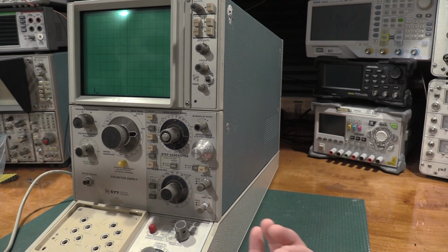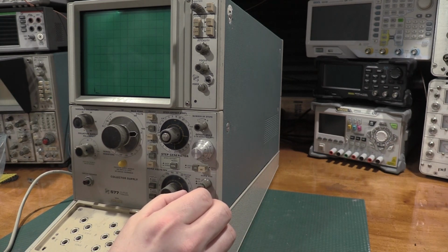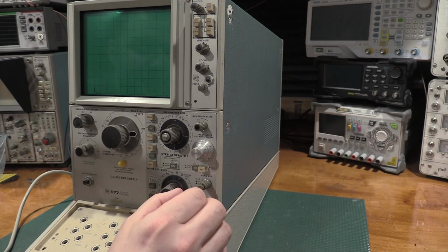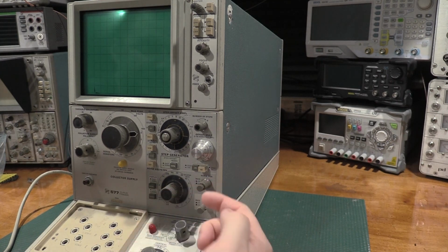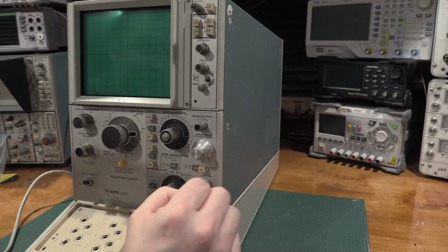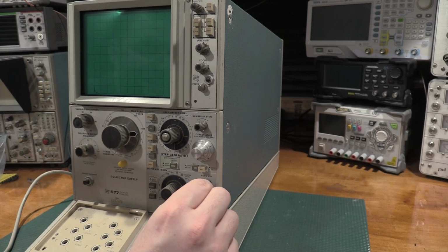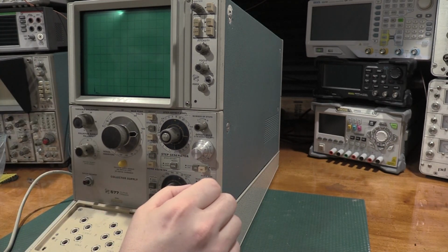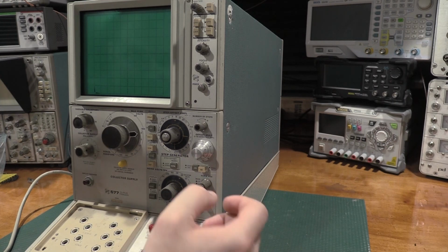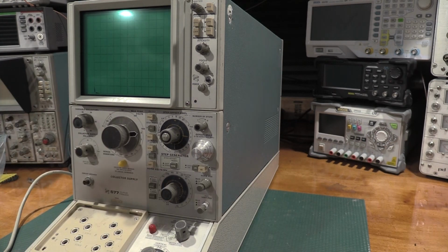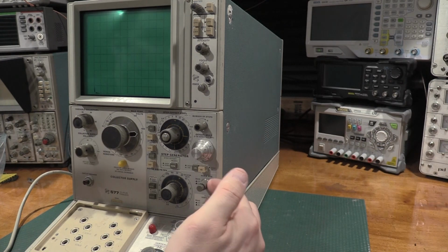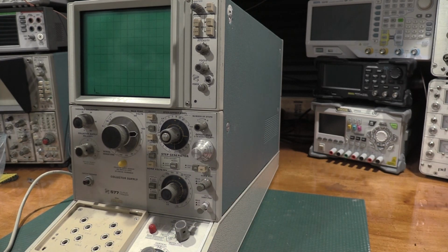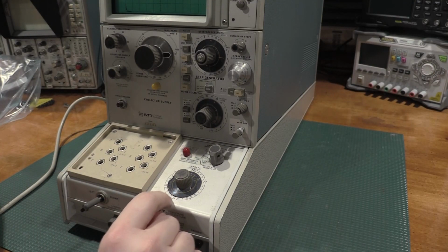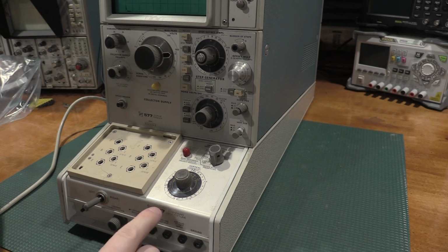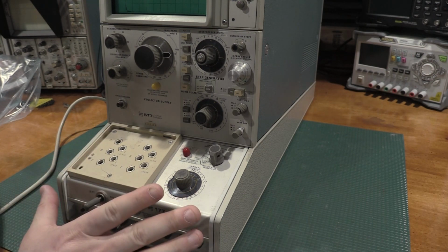The magnification existed in the first production, but it was pull out the control, and the control got really touchy because the control didn't change. This is actually a multi-stack pot where you have a main pot and then you have a zoom, which is engaging a same taper length but a lower value pot, so it's easier to adjust when it's in high magnification. The earlier versions didn't do that, so these controls are much easier to use on the improved version. This knob is a little different depending on which model or which generation of front porch you have.